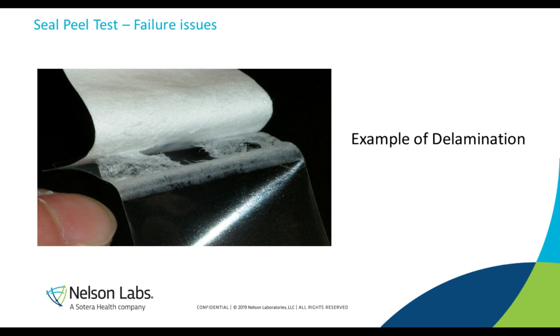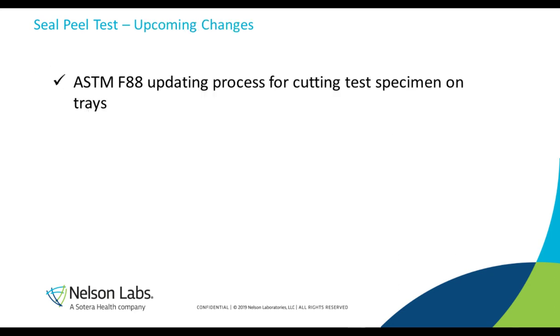This is another great example of delamination. I include this because a lot of nurses have issues with this creating fibers in the OR. So if you're having delamination issues, corrections to your sealing process would be necessary to ensure that you're alleviating the implication of particulates being released. A couple things, the ASTM is updating. They're looking at evaluating the actual process of not cutting out the coupons from trays. I know that the process itself is very difficult and can lead to variability in the results.